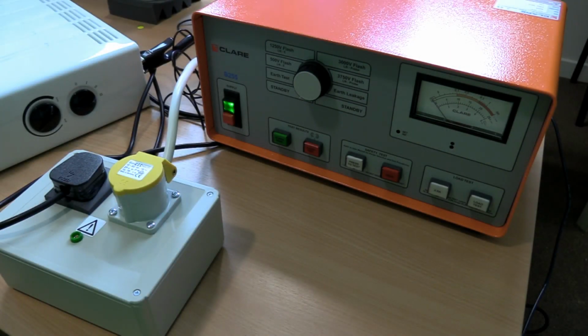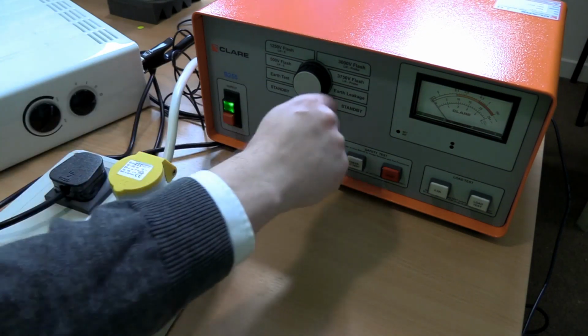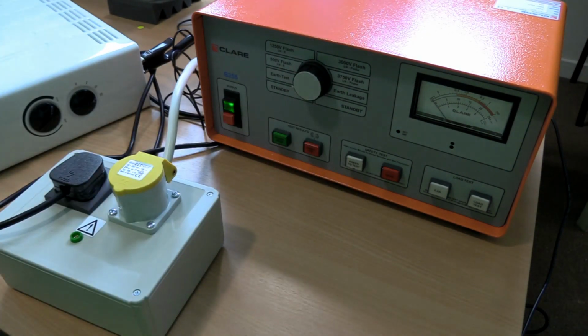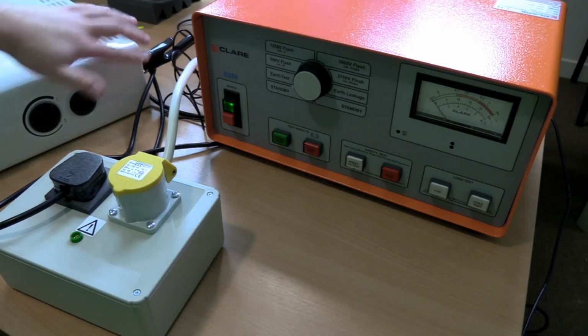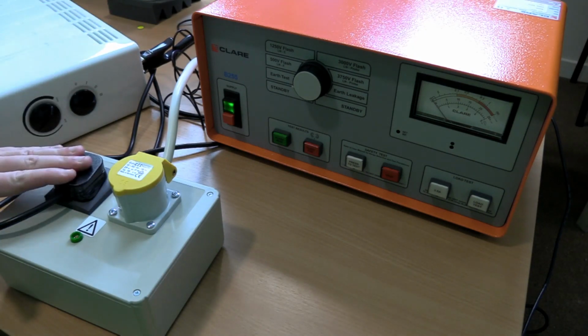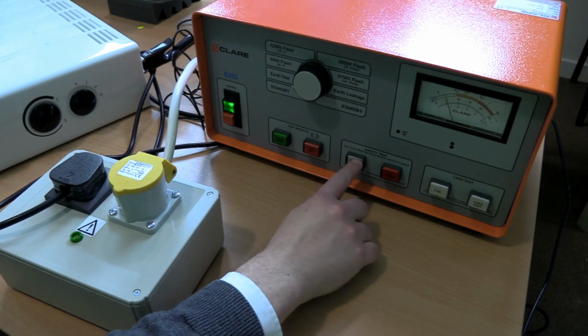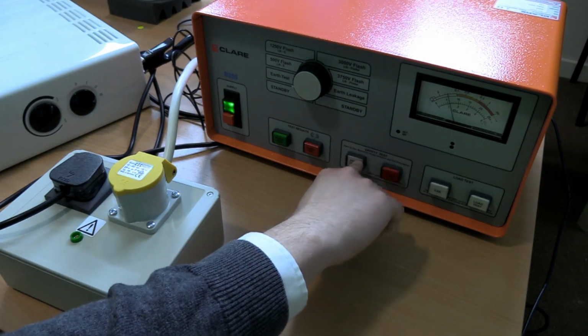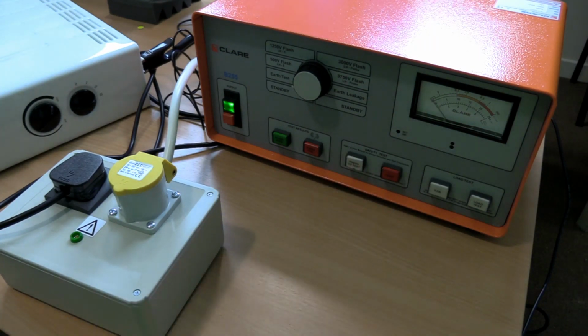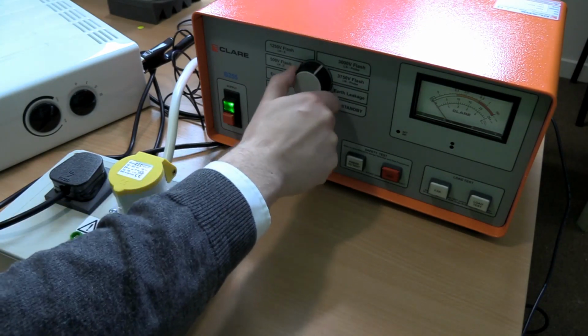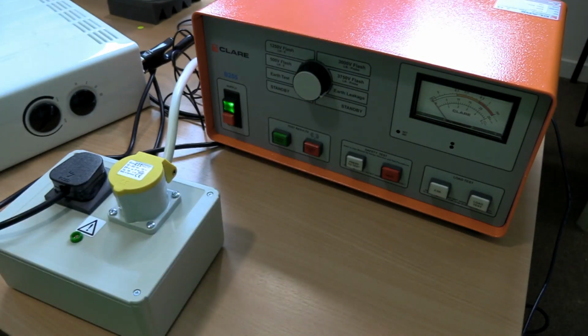So this time, using the B255, we're going to do an earth leakage test. Again, we're going to switch onto the earth test first. We've got our earth probe attached, make sure everything's turned on, all plugged in. We're going to run the earth test. We're in the good white pass area there, so we've got a pass on the earth, so we're safe to move on to the powered test. Turn it all the way around to earth leakage. Now this time it is going to power up the equipment, so just be aware of that.